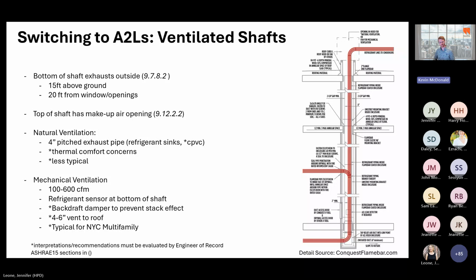So this is a messy slide, and there's a lot of information in the detail on the right of a typical detail of what a ventilated shaft might look like. But this is one of the key components and one of the more challenging aspects to fit into multifamily buildings. Basically, because refrigerant sinks, it can pool at the bottom, and it could be a fire risk. So we're ventilating the fire rated shafts that these refrigerant pipes travel in. And there's a few design considerations here.